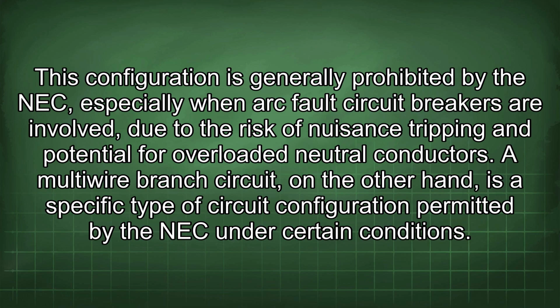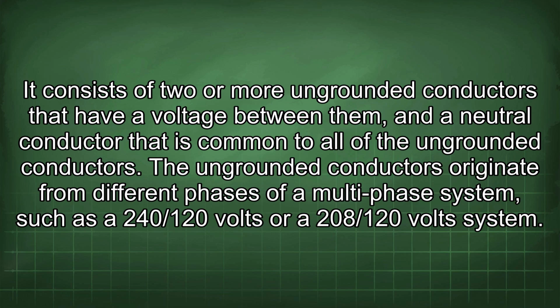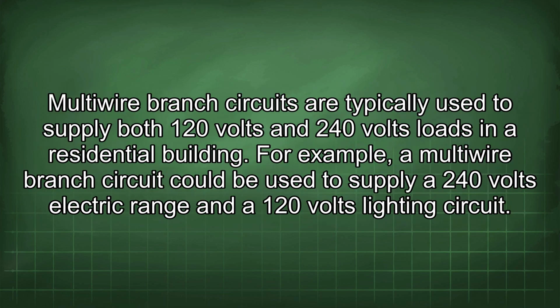A multi-wire branch circuit, on the other hand, is a specific type of circuit configuration permitted by the NEC under certain conditions. It consists of two or more ungrounded conductors that have a voltage between them and a neutral conductor that is common to all of the ungrounded conductors. The ungrounded conductors originate from different phases of a multi-phase system, such as a 240/120 volts or a 208/120 volts system. Multi-wire branch circuits are typically used to supply both 120 volts and 240 volts loads in a residential building.